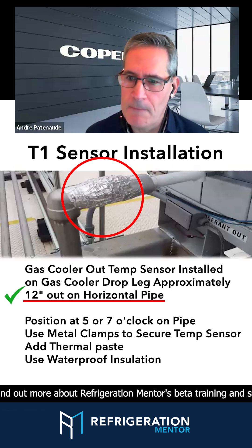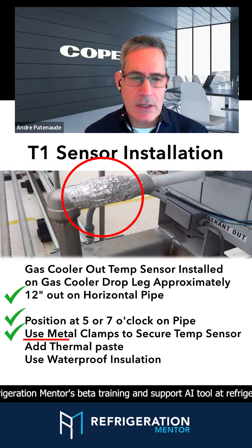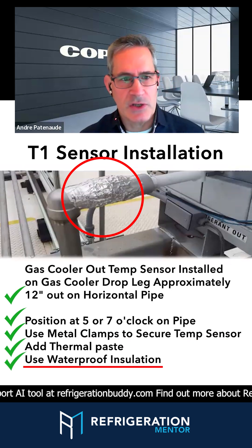On a horizontal run, 5 or 7 o'clock on the pipe, metal clamps — not tie wraps that break over time — thermal paste, and waterproof insulation.